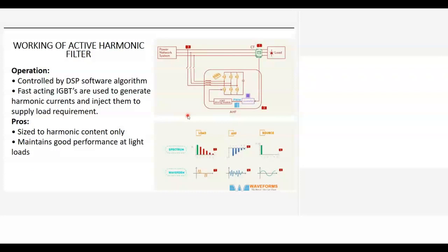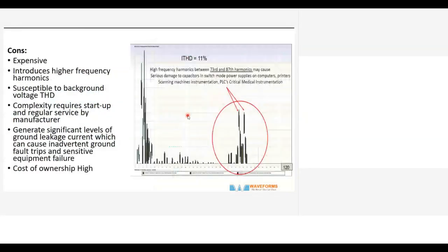So it is a complex electronic circuit involving microprocessors, DSPs, and IGBTs, and IGBTs are powerful electronic equipment, and they are prone to failure. Heat and dust all matter to the performance of the active filter. That is why it is expensive. And reliability is always a problem because it is totally electronics. And you can see that.